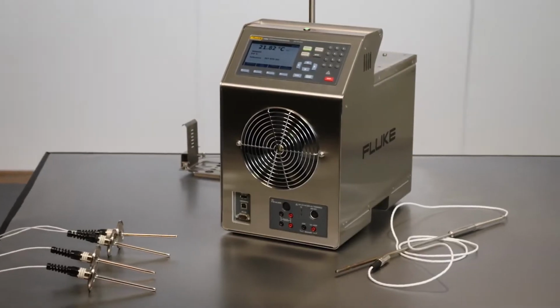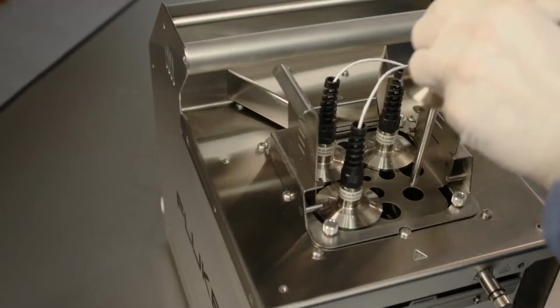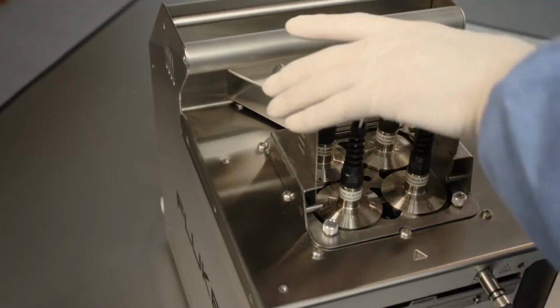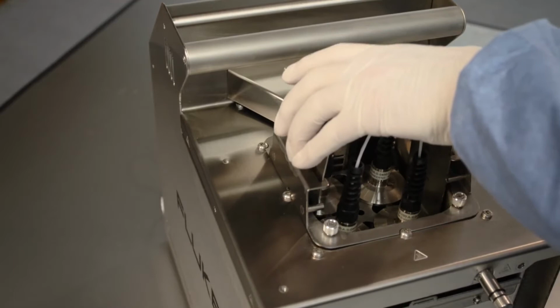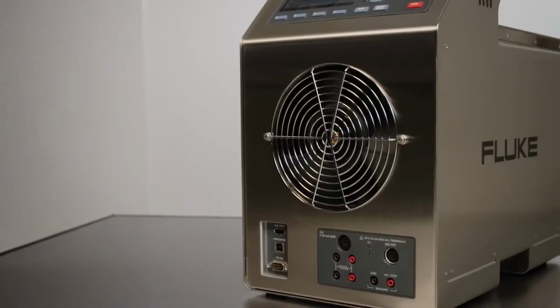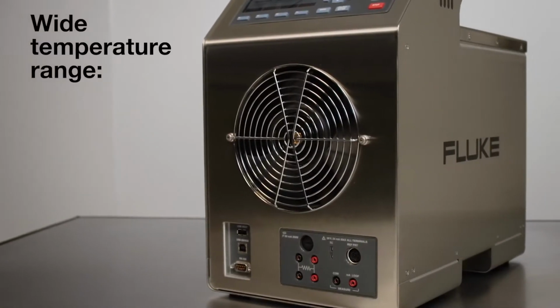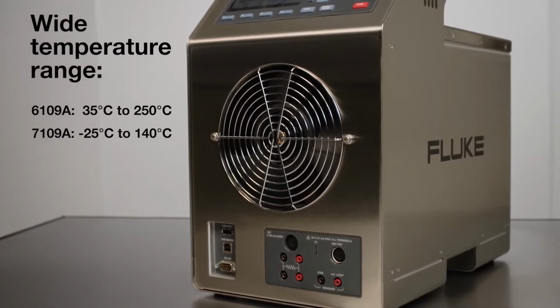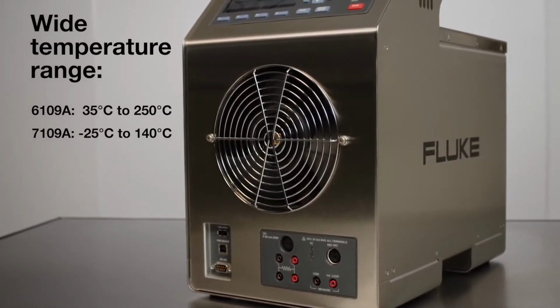Up to 4 tri-clamp sanitary sensors fit in these baths for calibration at 0.1 degrees Celsius display accuracy. The 2 bath models cover a wide temperature range, from -25 to 250 degrees Celsius.